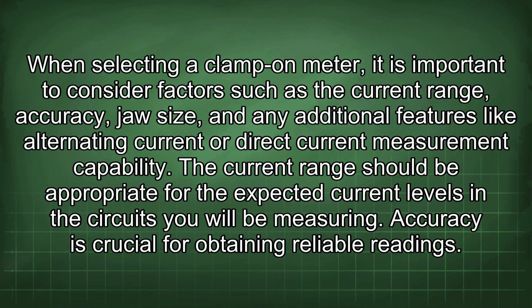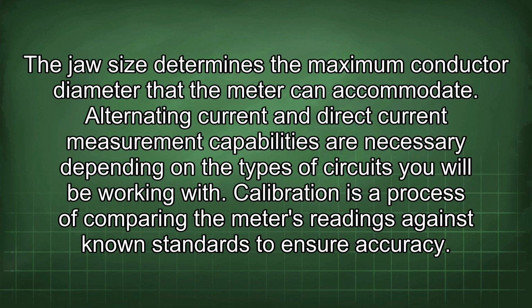When selecting a clamp-on meter, it is important to consider factors such as the current range, accuracy, jaw size, and any additional features like alternating current or direct current measurement capability. The current range should be appropriate for the expected current levels in the circuits you will be measuring. Accuracy is crucial for obtaining reliable readings. The jaw size determines the maximum conductor diameter that the meter can accommodate. Alternating current and direct current measurement capabilities are necessary depending on the types of circuits you will be working with.